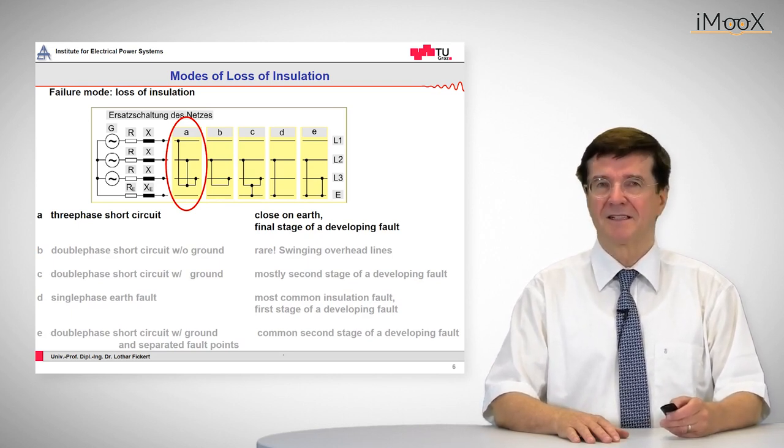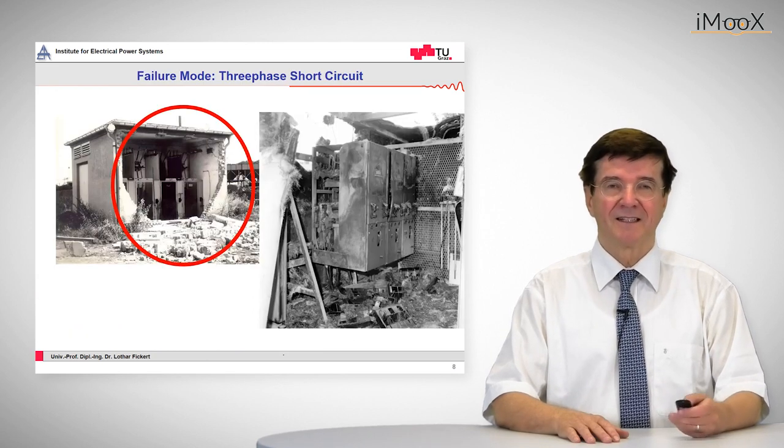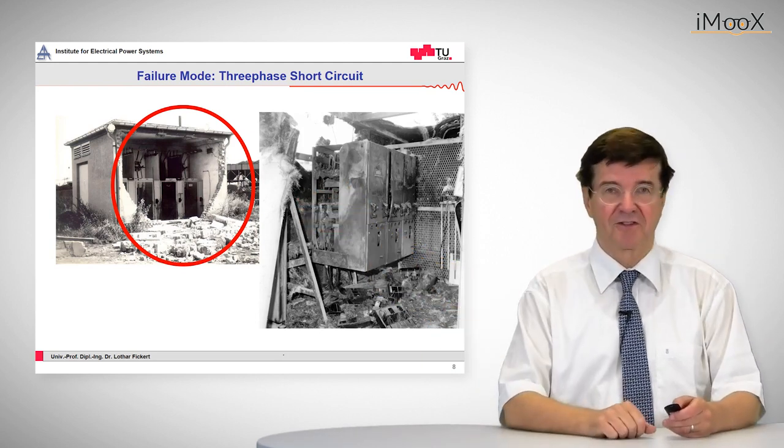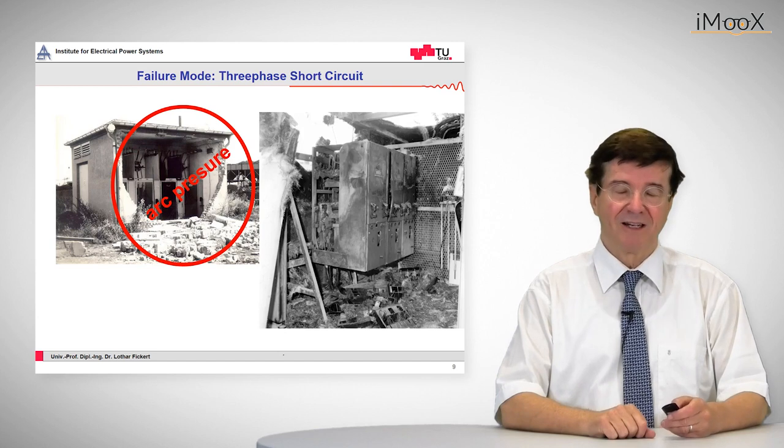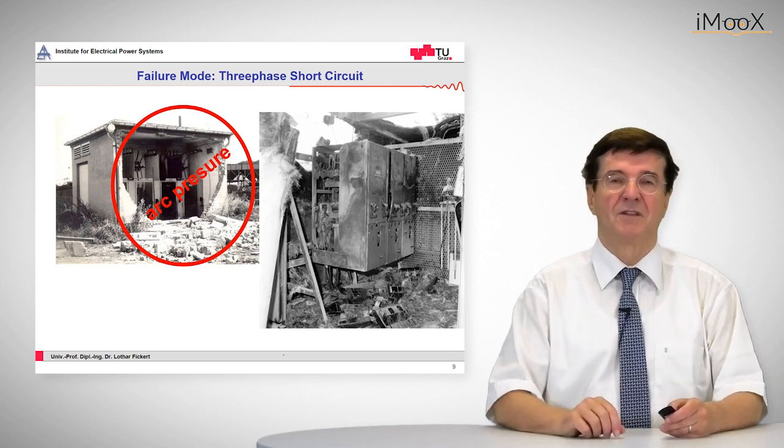First let's see some deplorable pictures of what happens. Let's see this building to our left side. The building has experienced a short circuit of some 20 kiloamps and the arc pressure has made the walls to explode and fall down.